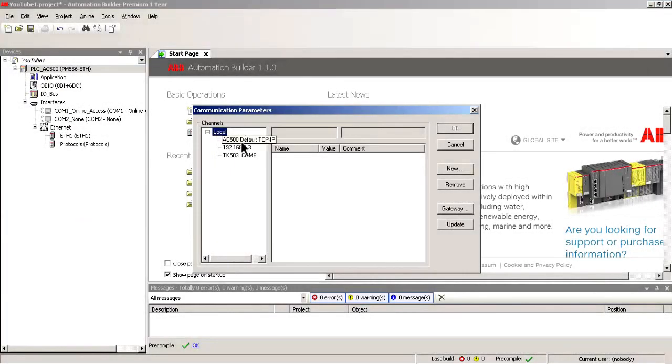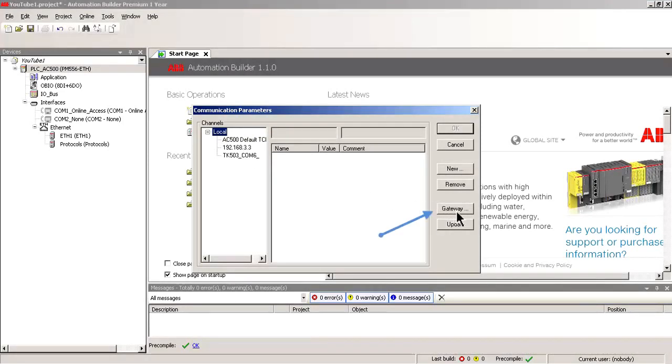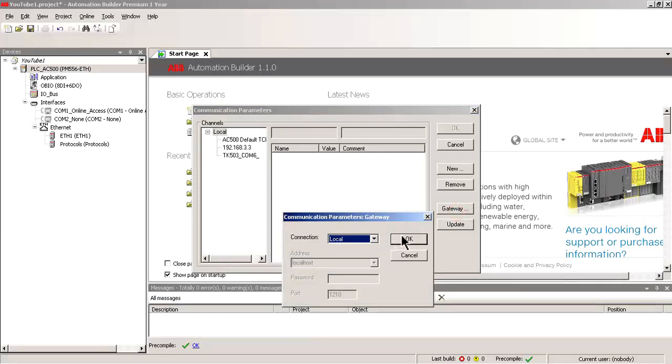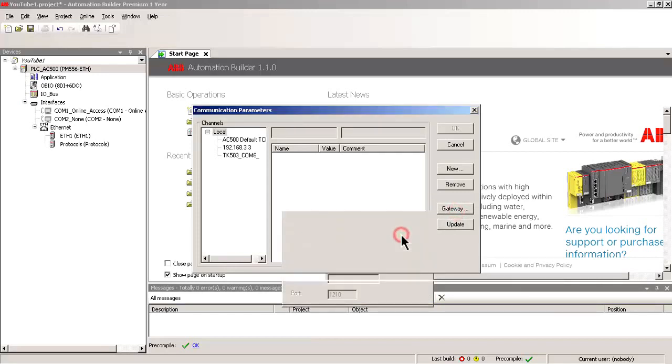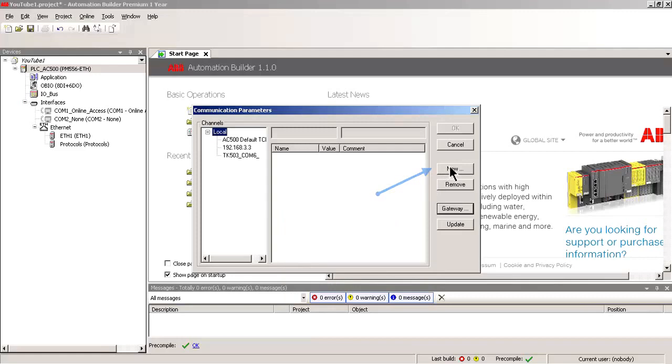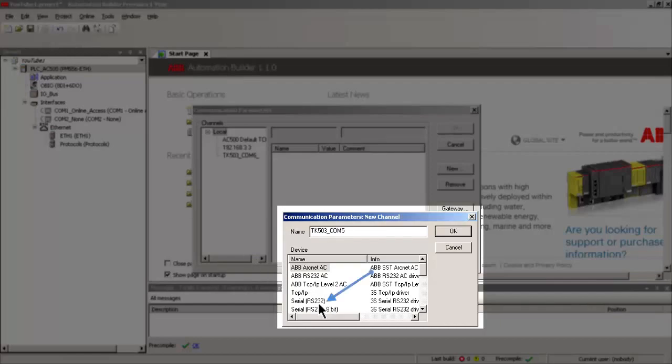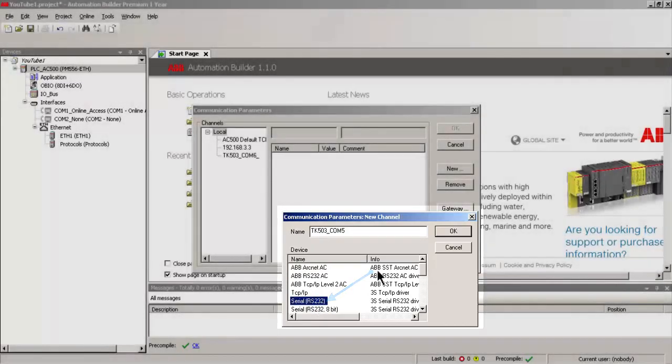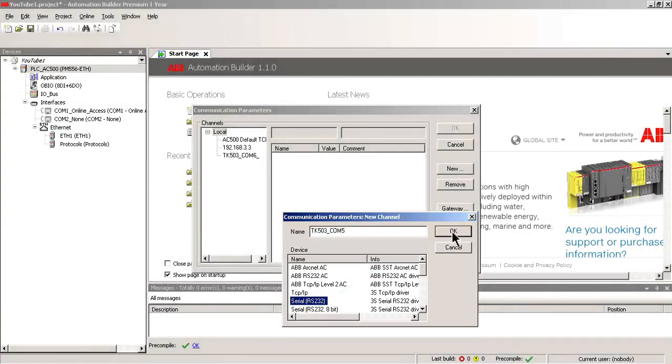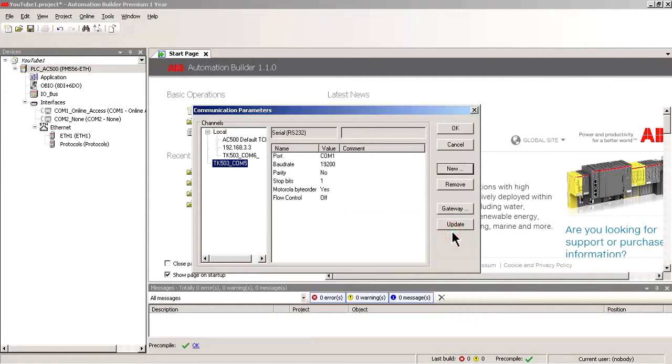You can see that in our local channel, we do not have a COM5 setup. So let's go to Gateway. Make sure we're installing on the local connection. And then click New to install a new connection. We'll call this connection TX503_COM5. This is a serial RS-232 connection. And we'll click OK.